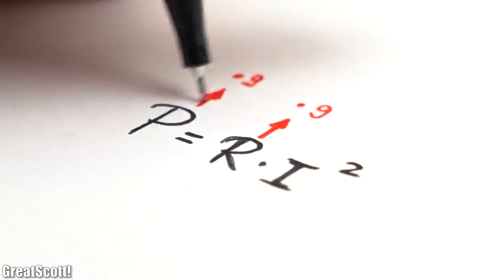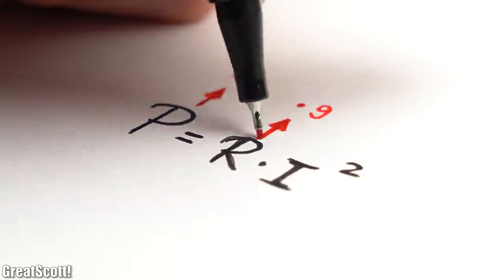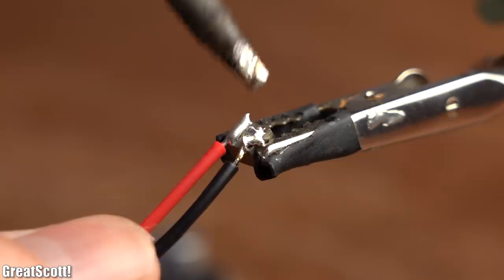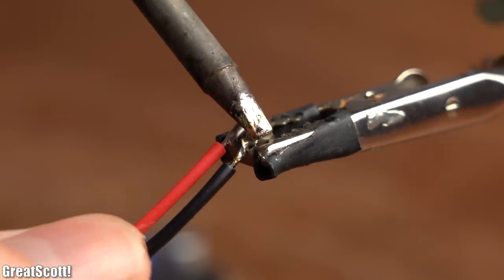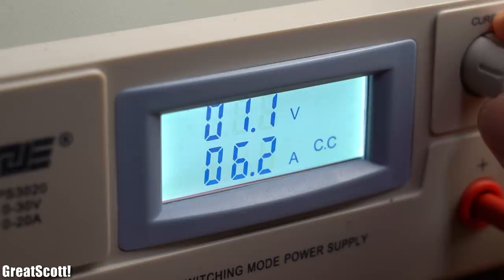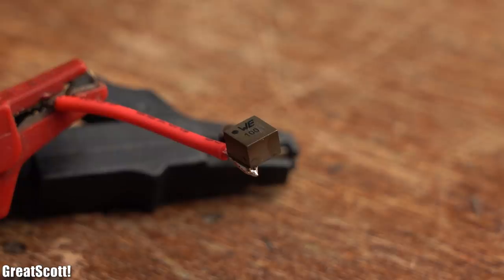And thus it produces nine times more power losses which need to get dissipated as heat. But because the smaller coil also features less surface area to dissipate the heat, we can easily slip into a region in which the winding insulation can melt and thus destroy the coil.